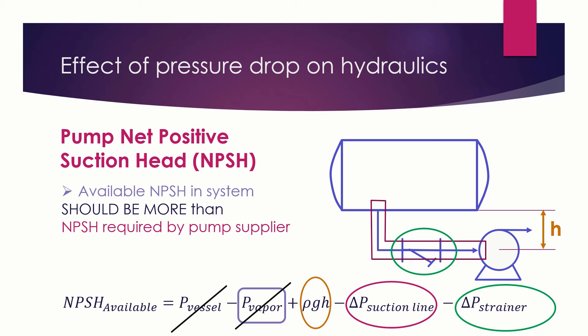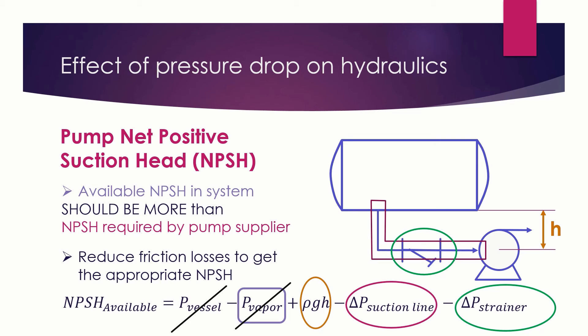One method to improve NPSH is to reduce the piping friction losses. This is not the only method — we can also increase the static head, decrease the pressure drop in the strainer, or choose a strainer which can give much less pressure drop. Another method is to increase the pipe size, which can ensure that losses in the pipe itself are minimized and can enhance the pump net positive suction head. In summary, increasing the static head and decreasing friction losses both increase the pump net positive suction head.